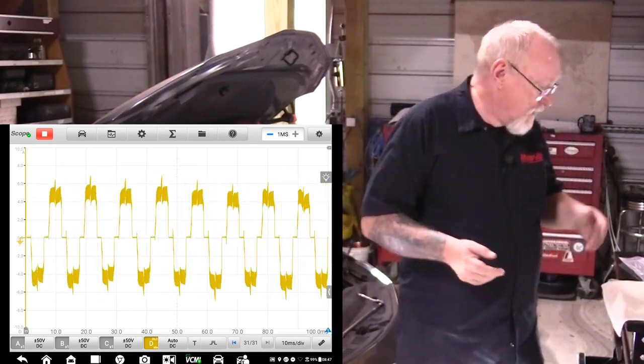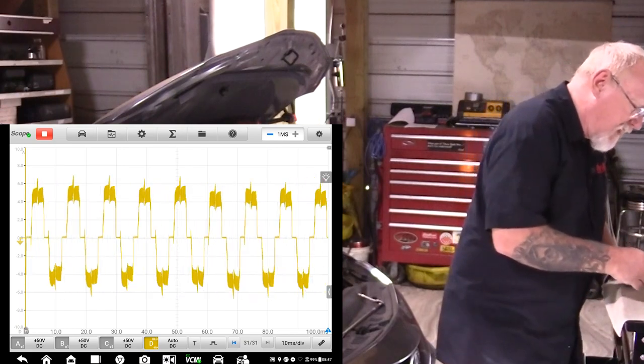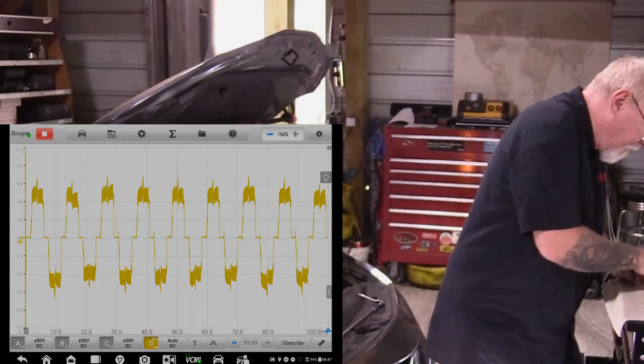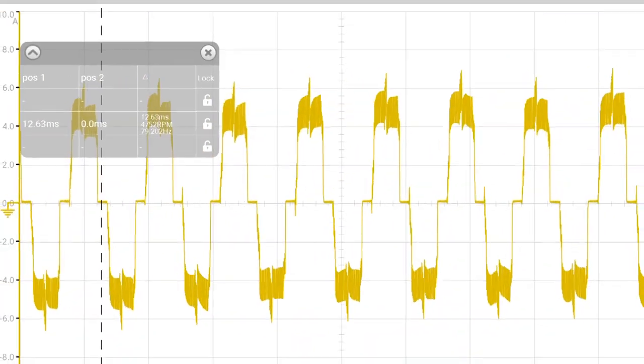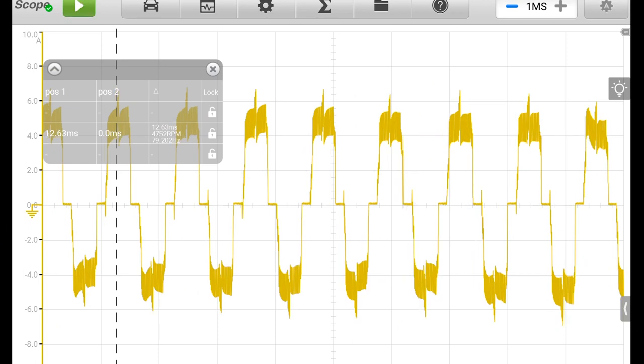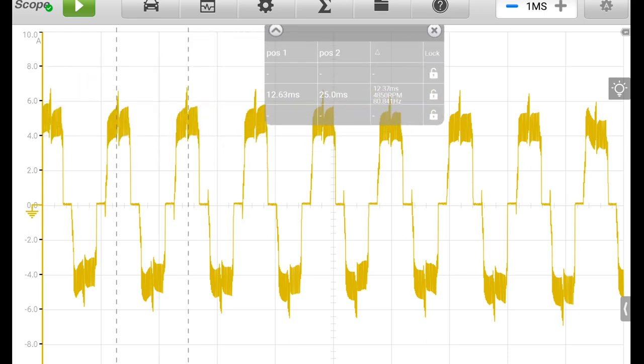Can we check that? Sure we can. What if we see if we can grab some cursors? We'll stop the scope there for a moment, and I'm just going to move them to the center of two up peaks and see what that tells us. Look real close, and it's reading 4,850 RPM, about 5,000 RPM for a pump speed.